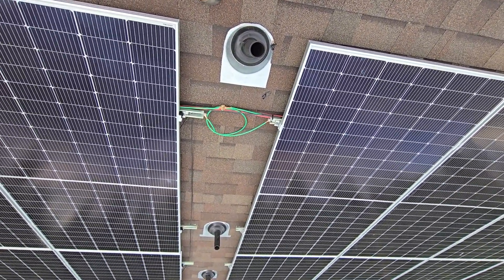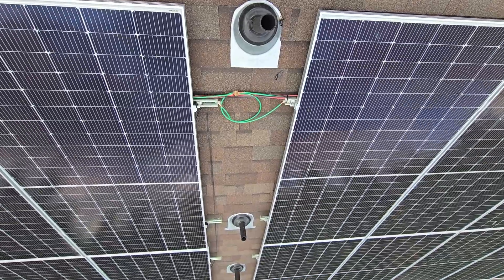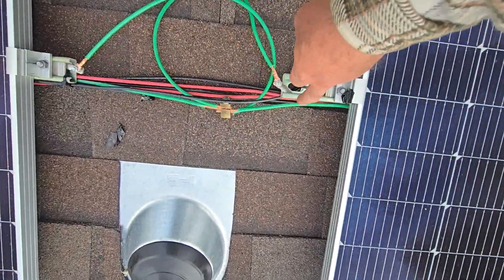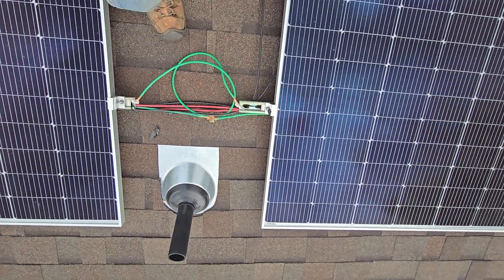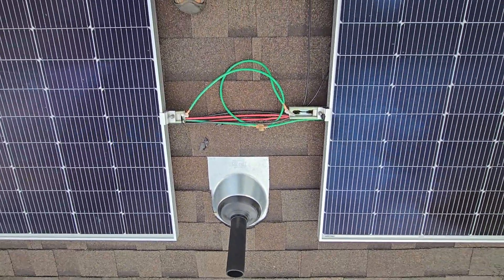I mean, you've got ground rods there, and that's what it's for. But you need to do it. So this is how I did it. I've used a bug nut — let me swing around here. I've got my main number six ground wire coming off the earth ground with two ground rods down over the edge of the house. Bug nuts wired in, so both sides of these are tied in to the ground assembly.